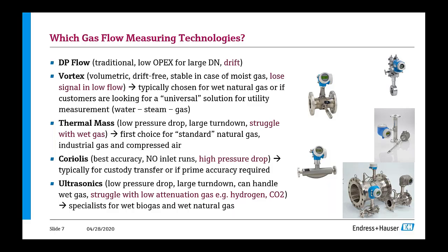But here in power plants, we find these applications. Primarily, you find them in custody transfer applications, so if you require prime accuracy. Then ultrasonics, they come with a low pressure drop, have a large turn down, and they can handle wet gas. But they struggle with low attenuation gases like hydrogen or carbon dioxide. And here we have some specialists for wet biogas and for wet natural gas.